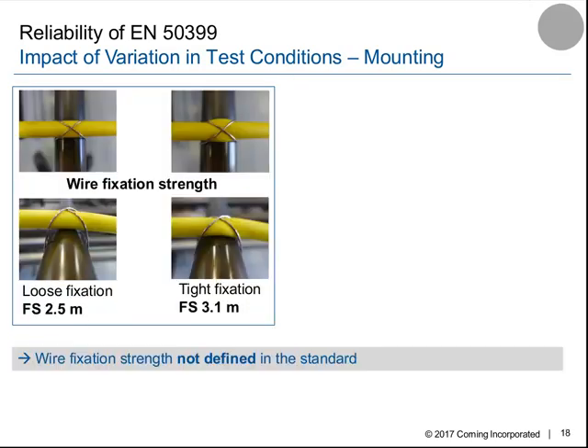The next thing about mounting is the wire fixation strength. The standard defines that the cable is fixed on the ladder with 2 wires mounted crosswise around the rung and the cable. But the strength with which the wire is fixed is not defined in the standard. So we took again a softer cable, because the calibration cable is too stiff to really mount it in a different way. With the softer cable, as you see here, we applied a loose and a more tight fixation. You also see that these are not really extremes. These are still within a normal variation range. However, if we look at the flame spreads, we see that the loose fixation delivers a flame spread which is lowered by approximately 60 centimeters compared to the tight fixation. But the fixation strength of the wire is again not defined in the standard.